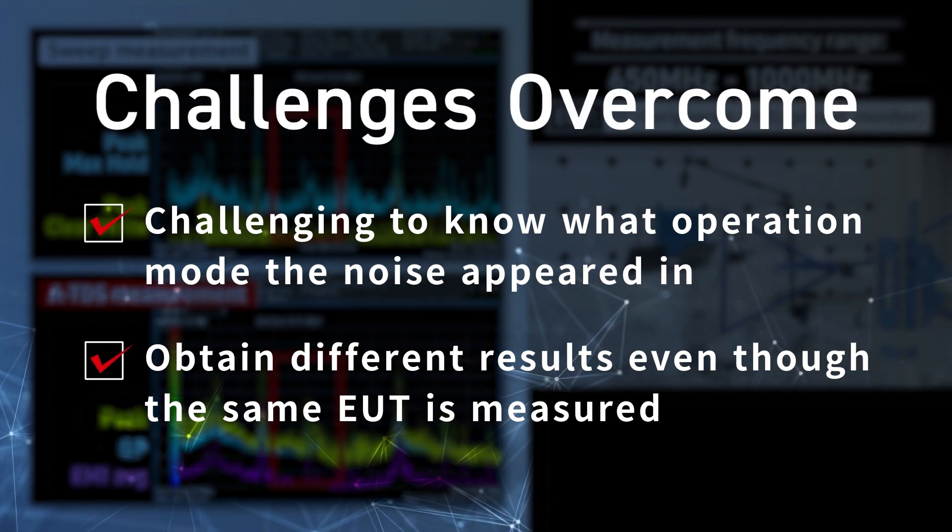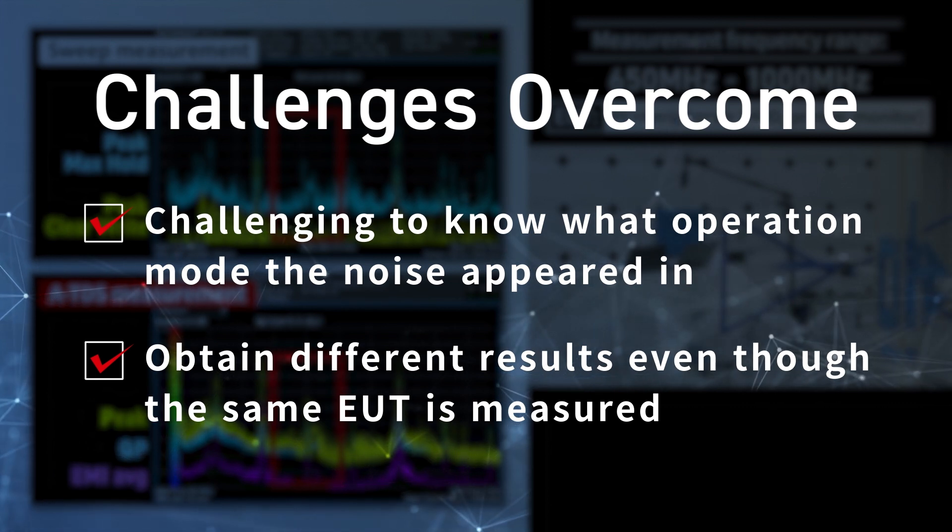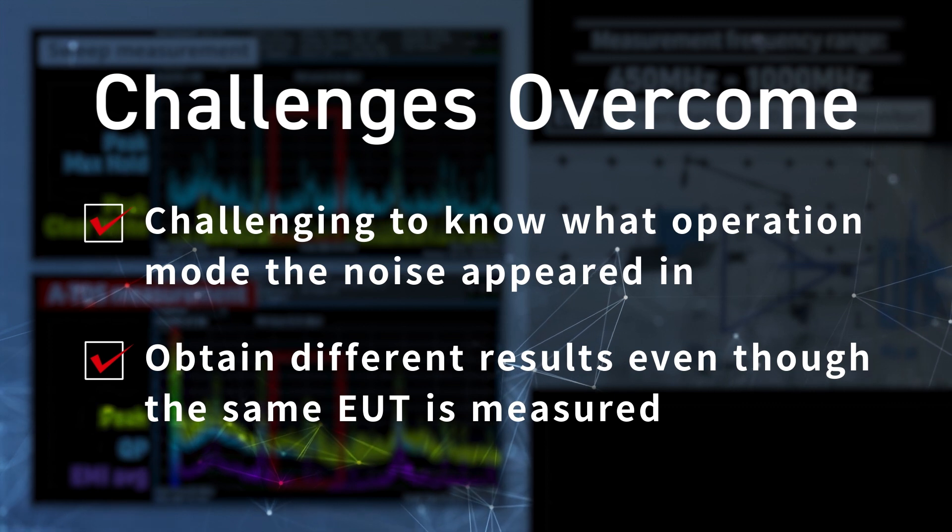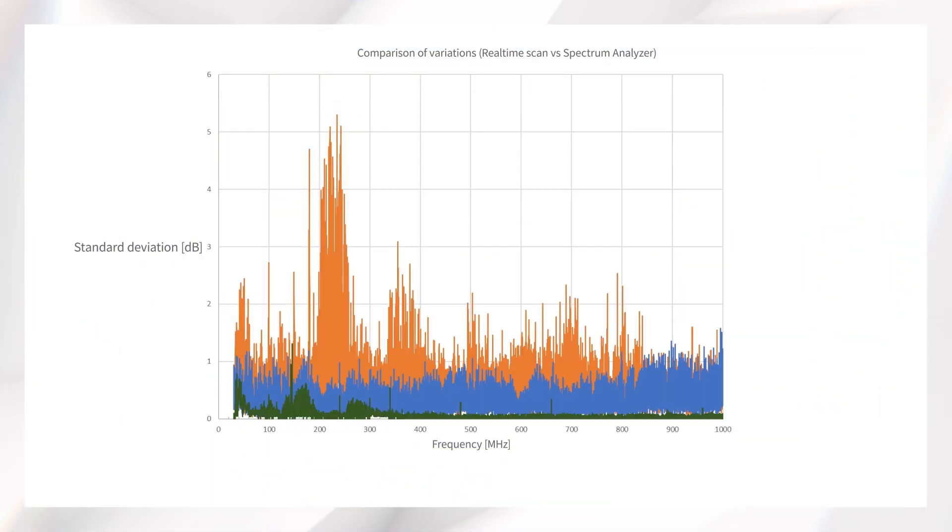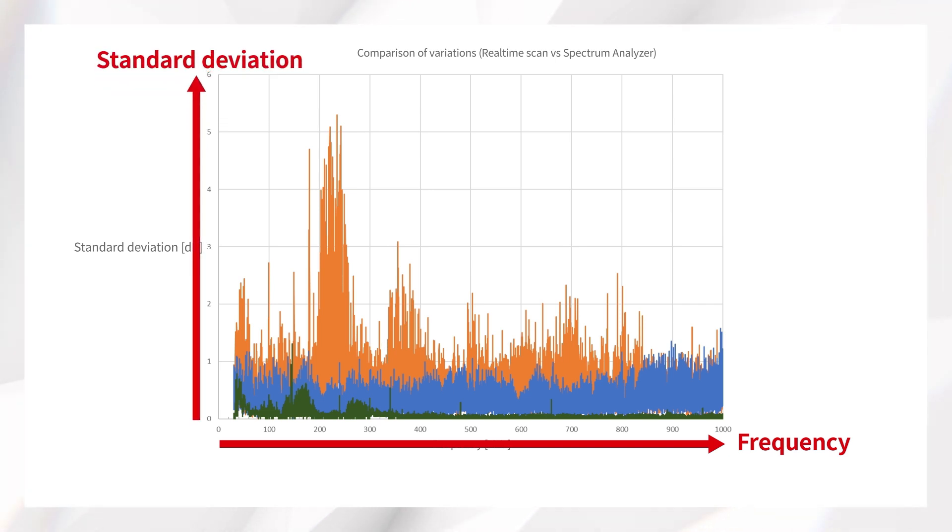Compared with the traditional sweep measurement, it helps substantially reduce the variations in the measurement values. The graph shows the variations in measurement results in both the sweep and ATDS measurements. The horizontal axis represents the frequency, while the vertical axis represents the standard deviation.